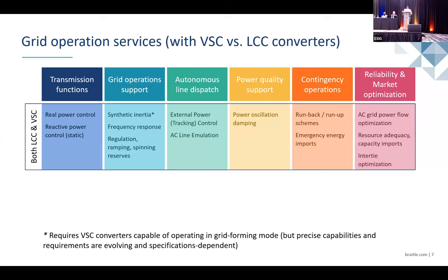For example, as we said here, external power tracking control. If you wanted, we can monitor one particular line's power flow, and when the power flow is increasing in that line, at the same time you can automatically increase power flow in the HVDC. Basically, we are distributing the power between HVDC and the neighboring AC system. And similarly, we can also use HVDC to improve power quality. For example, if there are power oscillations in the network, HVDC can modulate its output power into the grid, and thereby help to reduce power oscillations.